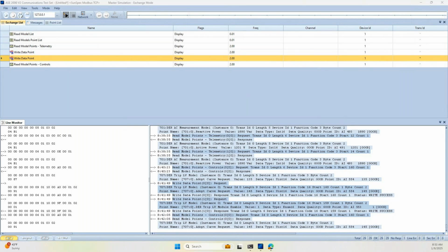Generally, the polling of the SunSpec Modbus is done at a rate of 30 seconds or 1 minute based on the utility requirements. SunSpec Modbus is built under Modbus, so that means the polling mechanism will have to be deployed. So I assume that's the intended question.